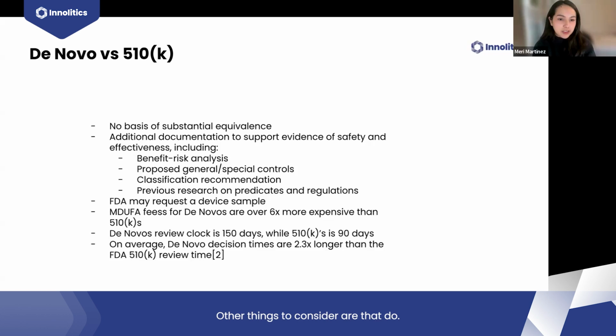Other things to consider are that MDUFA fees for de novos are over 6 times more expensive than 510(k)s, so definitely something to consider for our clients. And the de novo review clock with FDA is 150 days, while the 510(k) one is 90 days. However, on average, the de novo decision times are 2.3 times longer than the 510(k) review time.